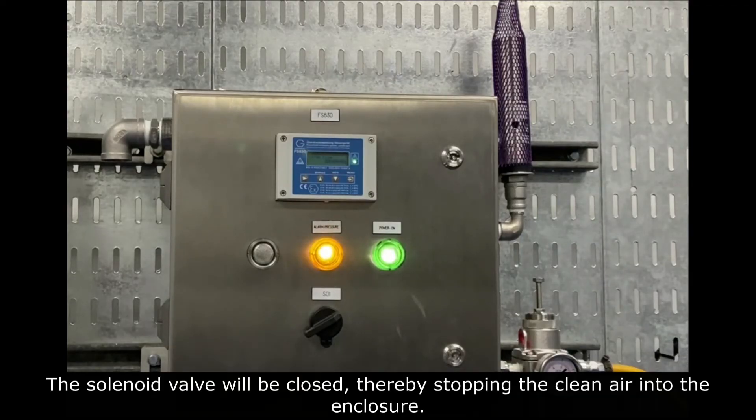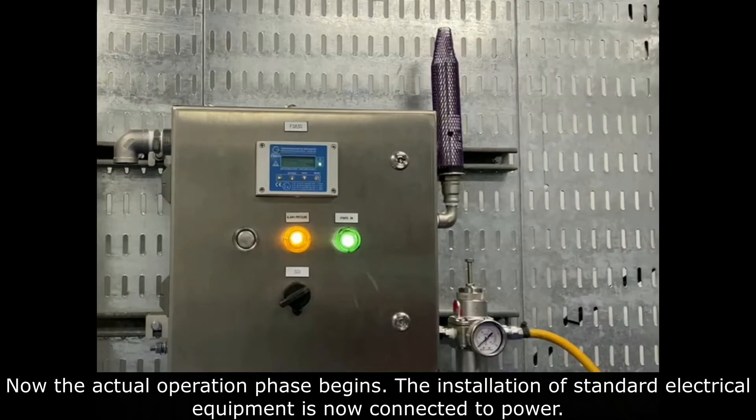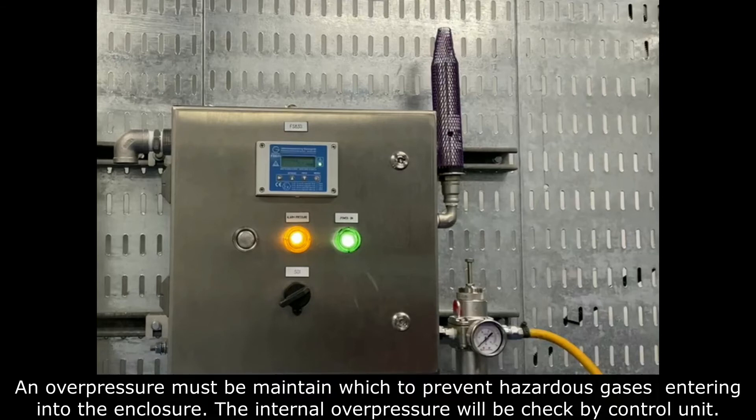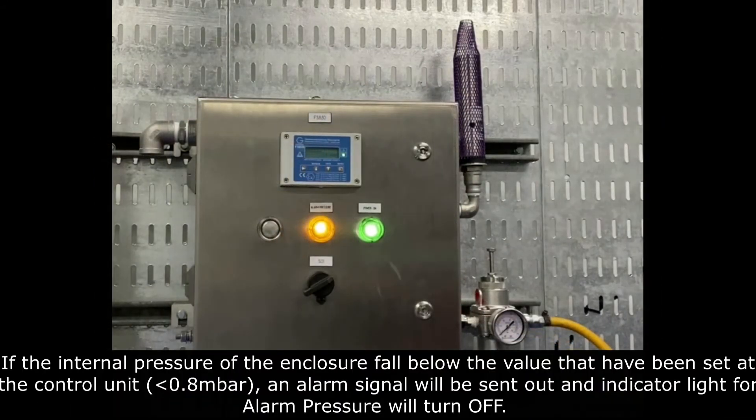The solenoid valve will be closed, thereby stopping the clean air into the enclosure. The control unit displays the current pressure reading and the light indicator will turn on. Operating Phase. Now the actual operation phase begins. The installation of standard electrical equipment is now connected to power. An overpressure must be maintained to prevent hazardous gases entering into the enclosure. The internal overpressure will be checked by the control unit. If the internal pressure of the enclosure falls below the value that has been set at the control unit, which is below 0.8 millibar.